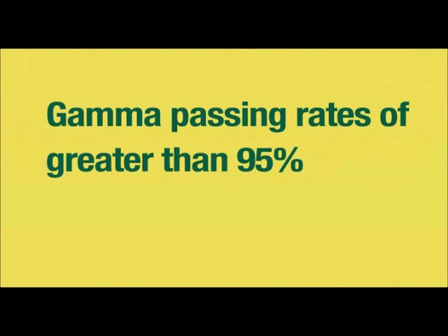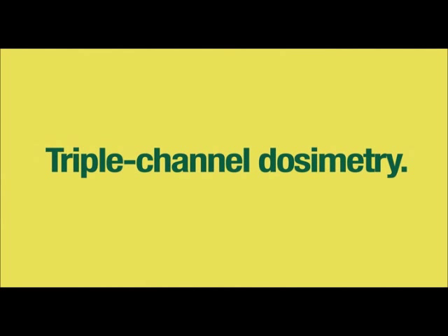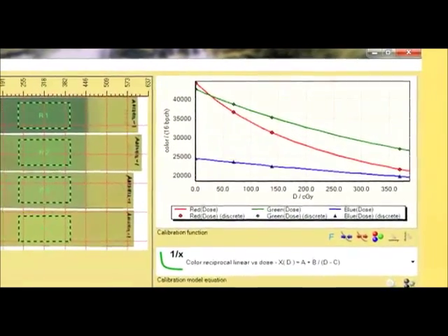And you get great results. Instead of 3% tolerance at 3mm, you get gamma passing rates more than 95%, 2% at 2mm. That could be your new performance standard. And only FilmQA Pro 3.0 uses triple channel dosimetry to deal with film and scanner artifacts. By looking at the consistency of results in all three color channels, you detect errors at any stage in the process. So FilmQA Pro 3.0 ensures the integrity of your measurements. Nothing else gives you that feedback.